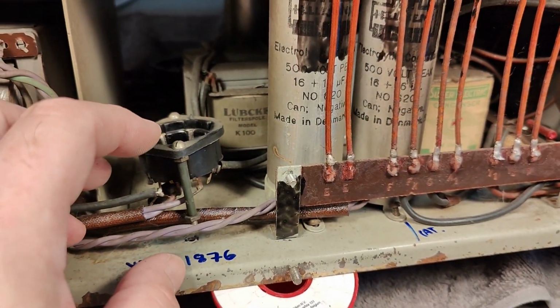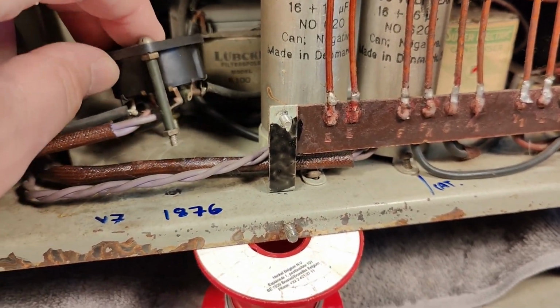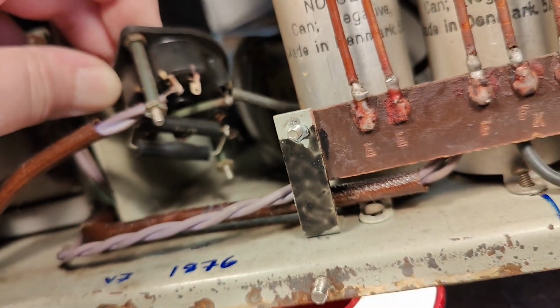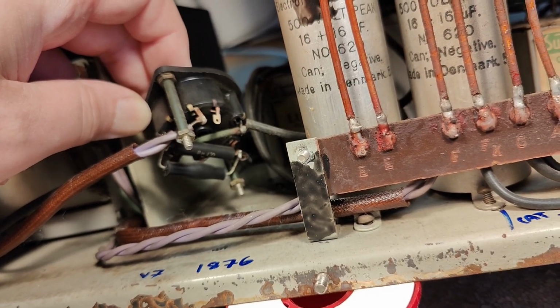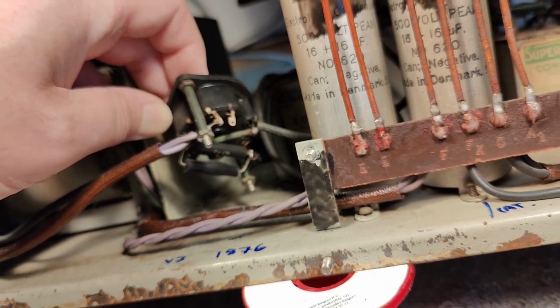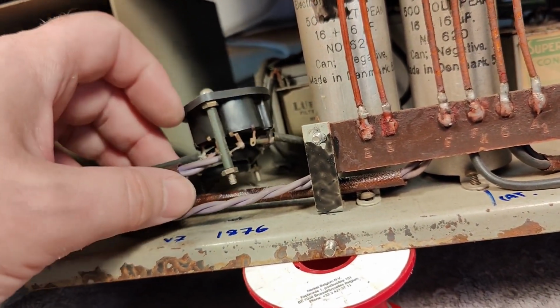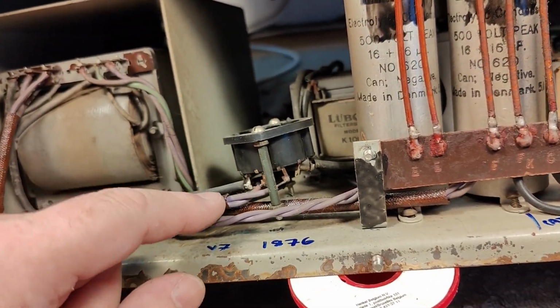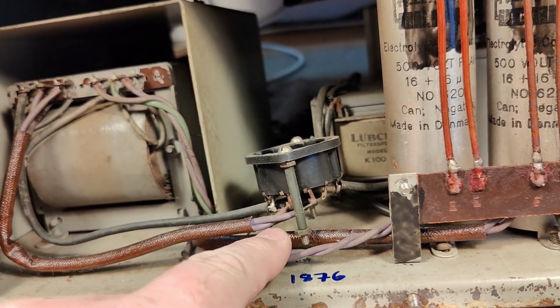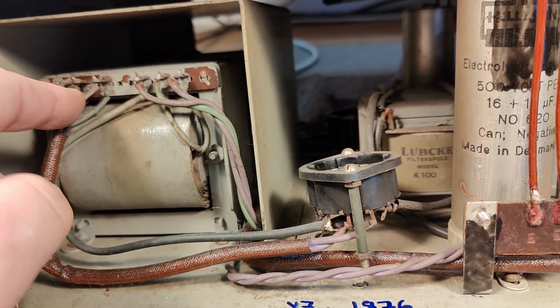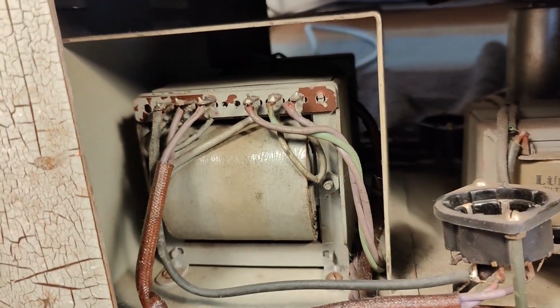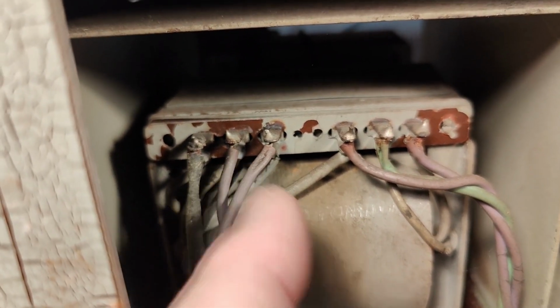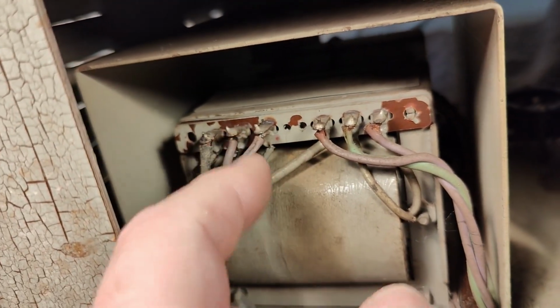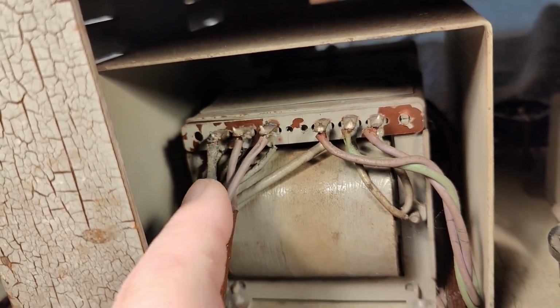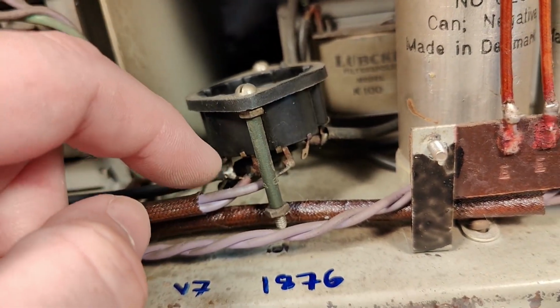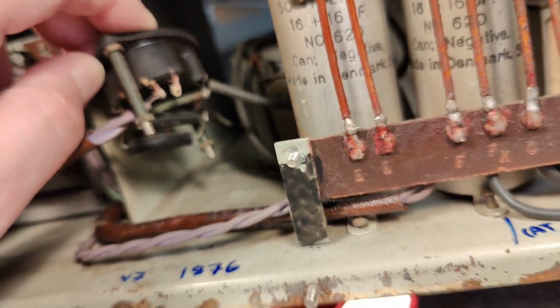And by the way, this is the high voltage, the cathode supply. And look underneath, we got some resistors right there, and they're supposed to be 0.1 meg or something. One of them is called 0.1 meg, but we got 2 resistors in series, and it's funny, it's mounted underneath this rectifier tube, because this is actually the return path. So we got these 2 wires here, and they're connected to the filament, but also to one end of the high voltage. I don't know if that is easy to see, but there are actually 2 wires on the middle one here. So that will be filament and high voltage. The other end of the high voltage is here, so that wire goes here.